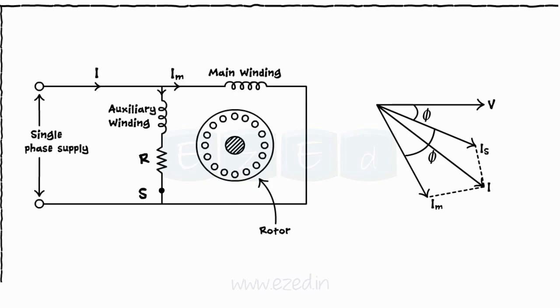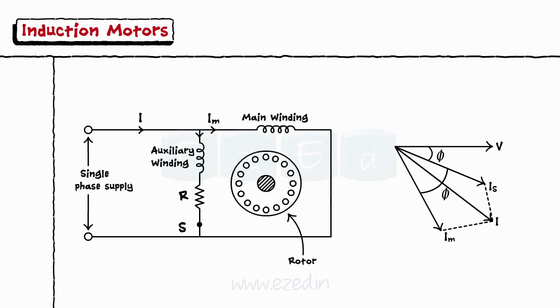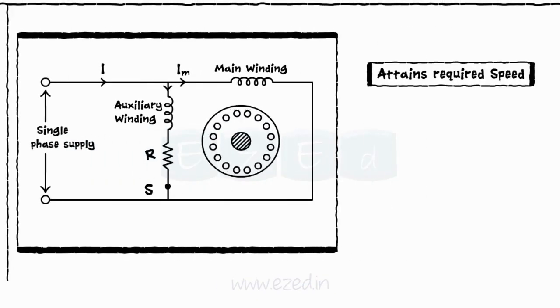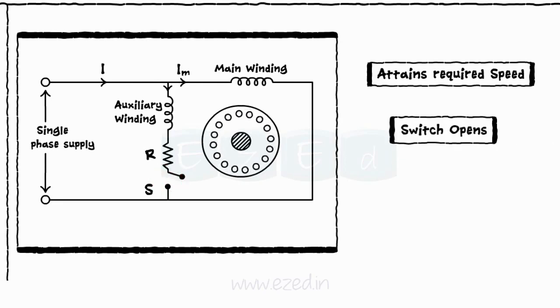Thus, IS lags behind applied voltage V by small angle whereas IM lags the voltage V by large angle. This creates the large split between two current phases. And as there is a split between the two currents, this motor is called split phase motor. Once the motor starts the rotation and attains considerable amount of speed, the centrifugal switch goes off disconnecting the auxiliary winding from the main winding, and motor continues to work on the main winding only.